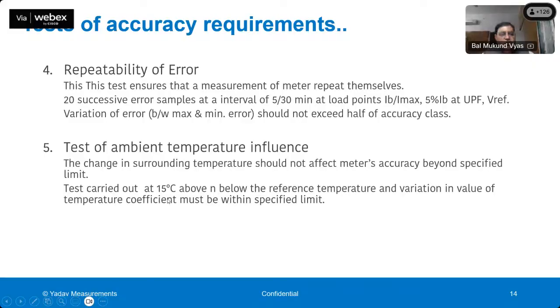Another very important test is the test of ambient temperature influence. As I told you, mostly the meters are installed outside the houses. Nowadays, you must have seen that meters are installed on poles also. When meters are installed under such harsh conditions, the meter sometimes has to face very high temperature. Sometimes meters are working under direct sunlight, and sometimes they have to face very low temperature also. So it is important that the accuracy of the meter is not affected and is within limits. Any change in error of the meter because of this temperature range should be controlled. This is the test which ensures that the meter's accuracy is not highly affected by temperature.